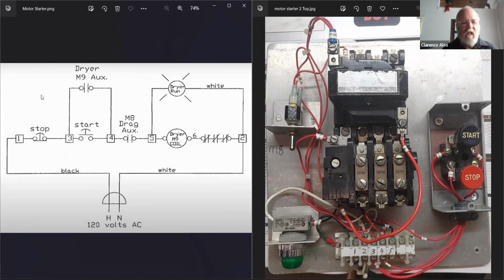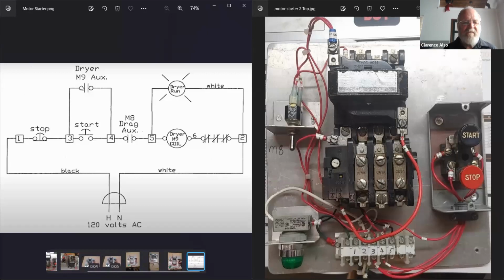So first of all, let's pick on this first wire right here. How can we tell if that first wire is good? What are we expecting on the 3 side of that auxiliary contact? Here's the 3 side of the auxiliary contact. What are we expecting there? 120, when the button's pushed in, your start button's pushed in.